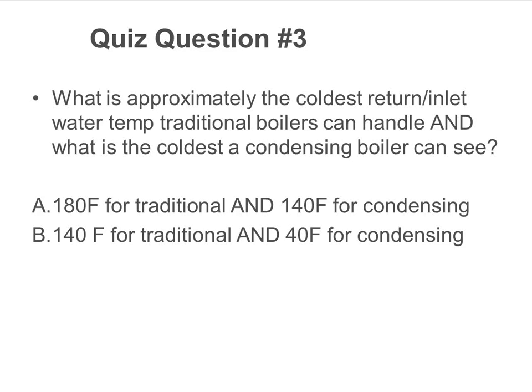Make sure you got a decent sized drain available, because when they first start up, they condense like a bear. Okay, which is fine, and they love it. And just so you guys can see real quick, since so many of you didn't get that one, on that chart, we want to go as cold as we possibly can. So if I get it from 90 to 40, I'm going to get another, in this example, 5% more efficient by doing that. So I definitely want to take that 40 degree water if I can get my hands on it. Nothing wrong with that at all.